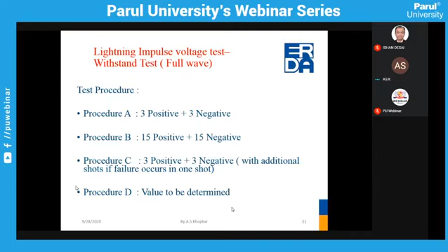In procedure D, we'll have to find out the value. Now, as I told you, in the withstand value, chopped wave is also there. So this is the chopped wave which we are using in the laboratory. Here we'll have to apply the test voltage, and chopping time we'll have to maintain 2 to 5 microseconds. And in case of chopping, most of the time it is negative polarity, not positive polarity. And whenever chopping occurs, only single polarity test is enough.